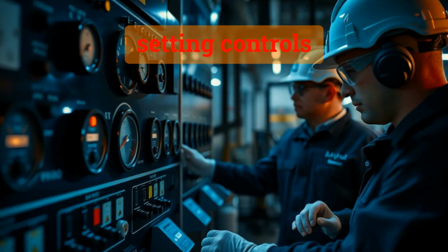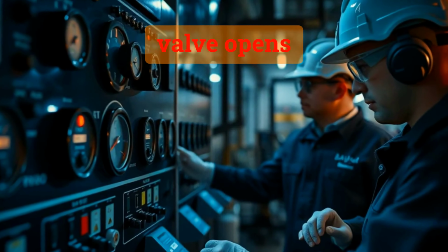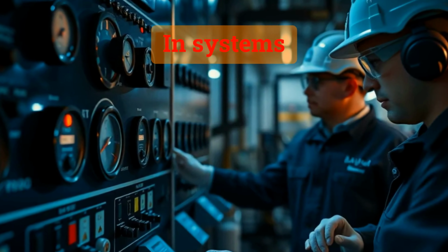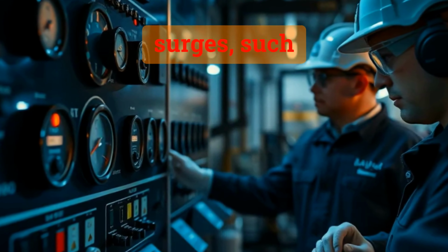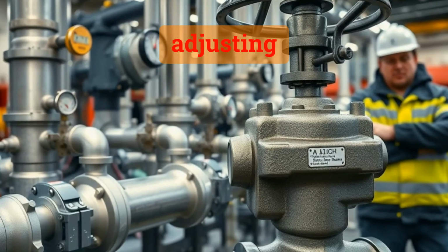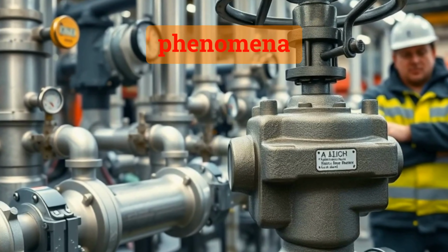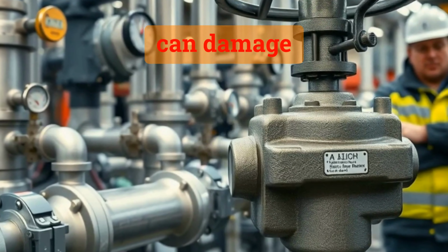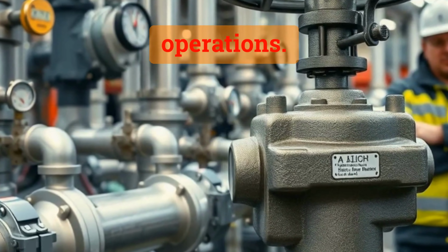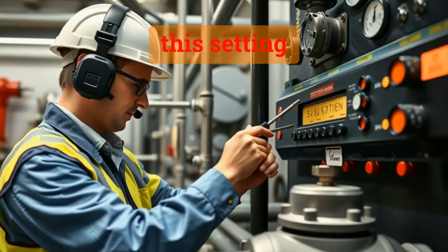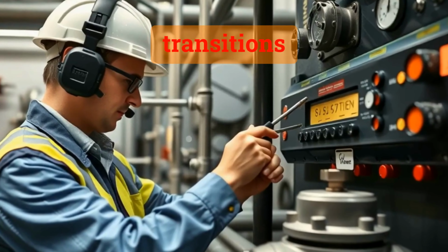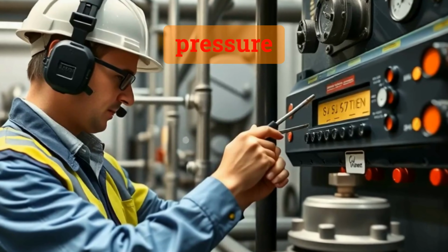Valve stroke speed setting controls how quickly a valve opens or closes. In systems sensitive to pressure surges, such as water pipelines, adjusting the stroke speed helps prevent phenomena like water hammer, which can damage equipment and disrupt operations. Fine-tuning this setting allows for smooth transitions and protects the system from abrupt pressure changes.